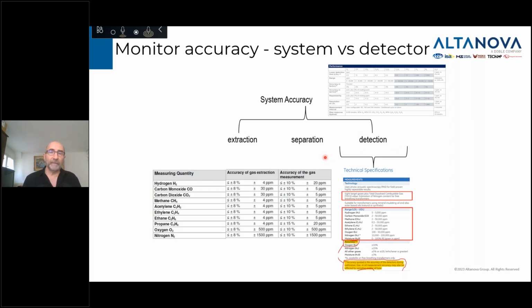So when you look at it, everyone writes their spec differently. Some people will show the accuracy of the gas extraction in one way, and then the accuracy of the gas measurement. And that's right, it's one way of doing it. But if you really want to understand how good their system is, you have to add them together. So specifically, when you write a spec like that, what it means is that, let's say for hydrogen, your accuracy now is 18%. And if you're looking at the fault gases, especially the gases used in all the different diagnostic tools I showed earlier, the methane, the acetylene, the ethylene, and ethane, well, together, the accuracy of that system, brand new equipment right from the beginning, has an accuracy right away of 18%.